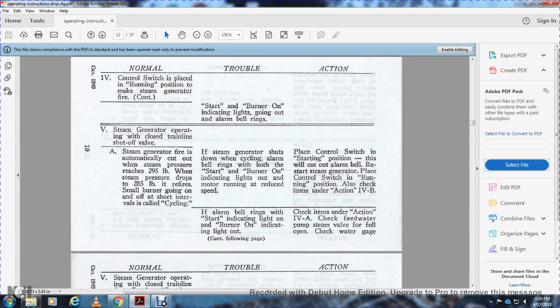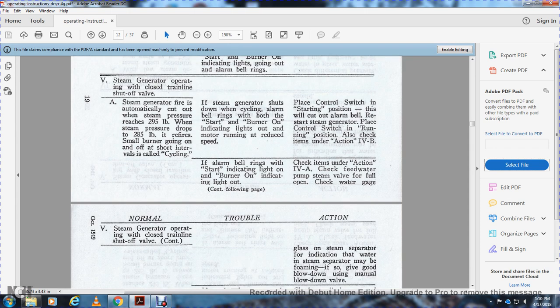If the alarm bell rings with the starting indication light on and the Burner On indicating light out, check the items under the action of item 4A, with a check of the feed water pump steam valve, with the valve open, and a check of the water gauge glass on the steam separator. The water in the steam separator may be foaming. If so, give a good blowdown using the normal manual blowdown valve.